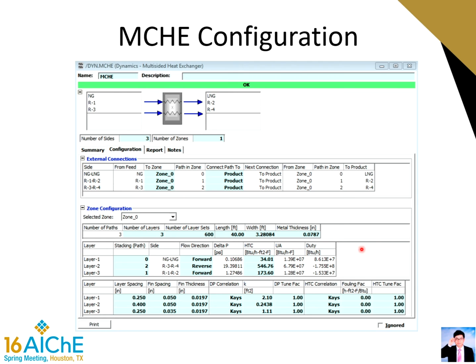The main heat exchanger is modeled as a plate-fin type exchanger. The total length is 40 feet with a width of 3.3 feet. There are a total of 600 layers, with each stream having about 200 layers — we may need several cores for the heat exchanger. Each layer has its own layer spacing and fin spacing. To speed up the calculation, the heat transfer coefficient is not calculated; instead, it is assumed to be a fixed value taken from another heat transfer software.